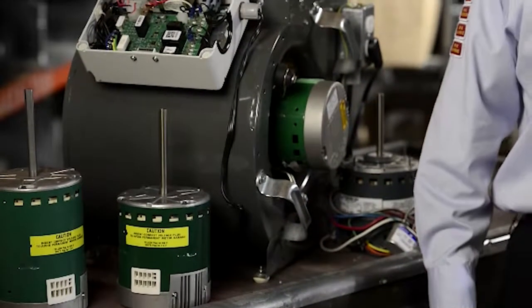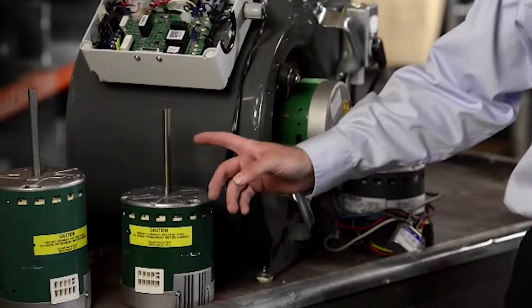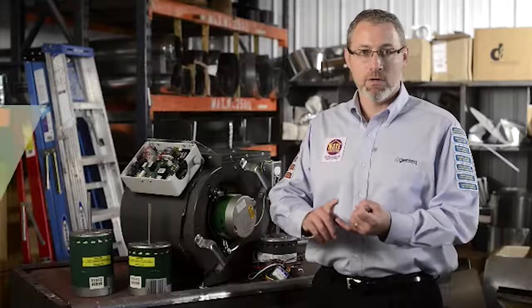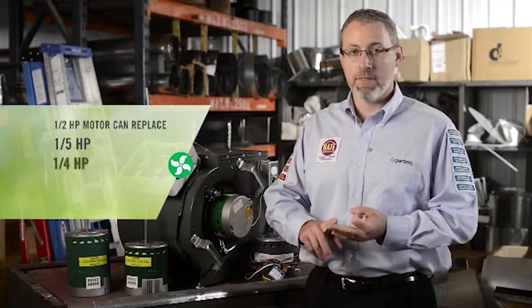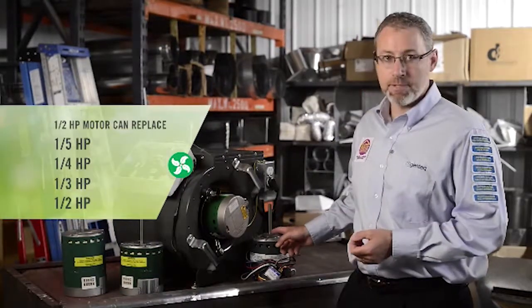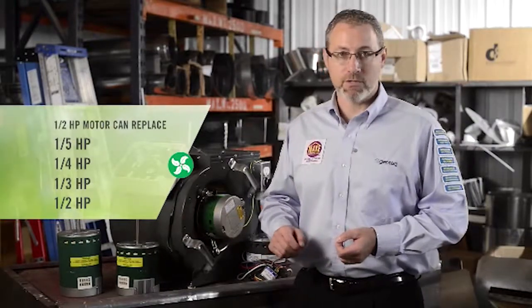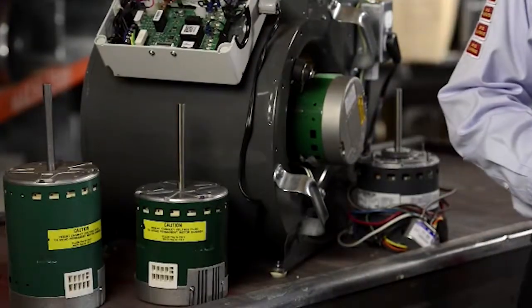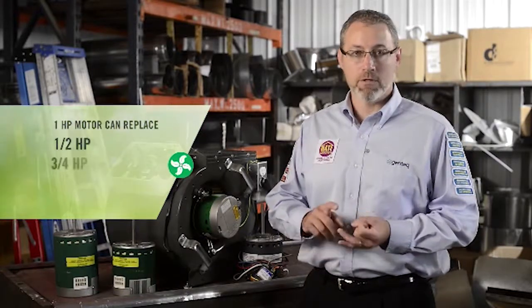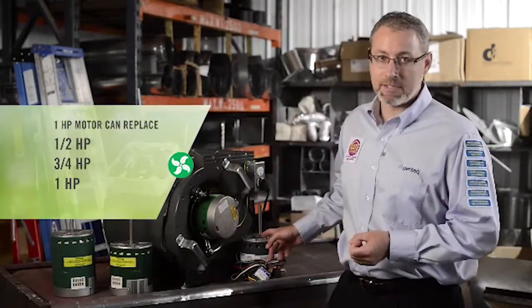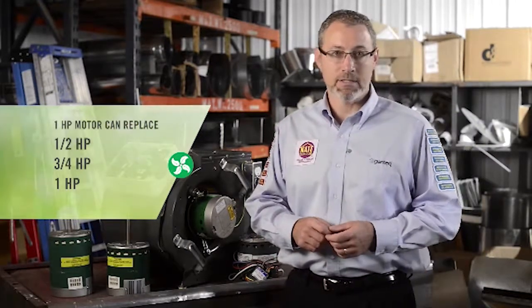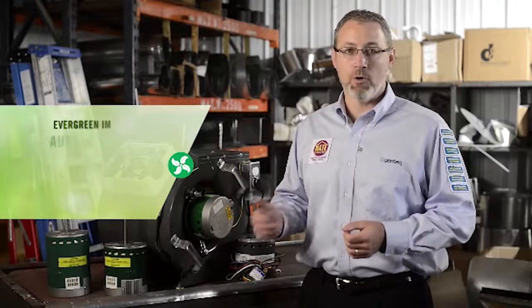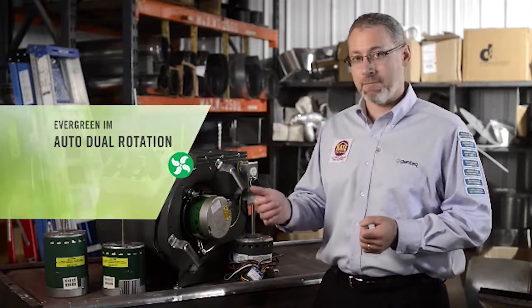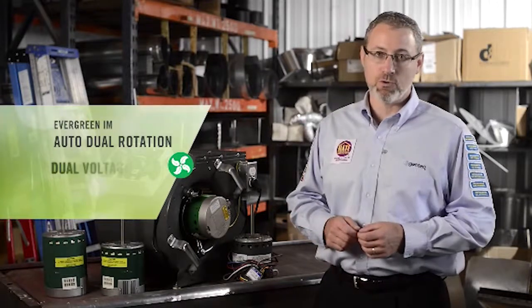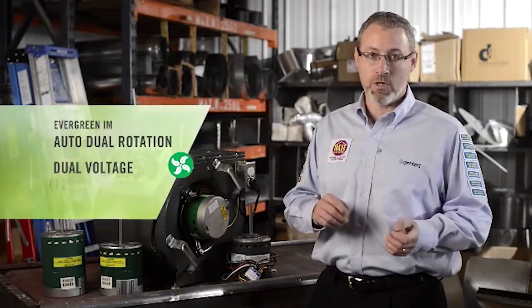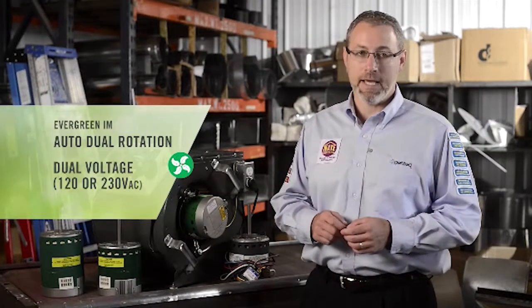The Evergreen IM is built in two versatile sizes. The 1/2 horsepower motor can replace 1/5, 1/4, 1/3, and 1/2 horsepower PSC sizes. Its stock number is 6005. The 1 horsepower motor can replace 1/2 horsepower, 3/4, or 1 horsepower PSC motors, and its stock number is 6010. Both motors are dual rotation, and that's automatic dual rotation. Both motors are also dual voltage. They can be operated at either 120 or 230 volts AC.